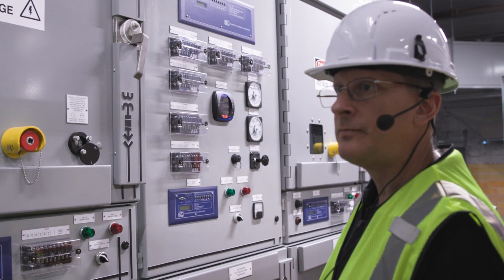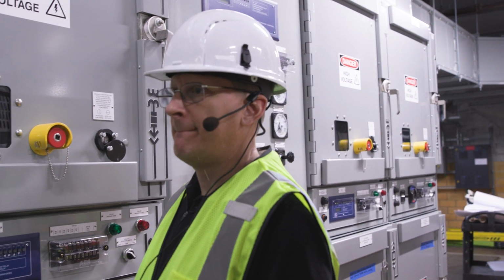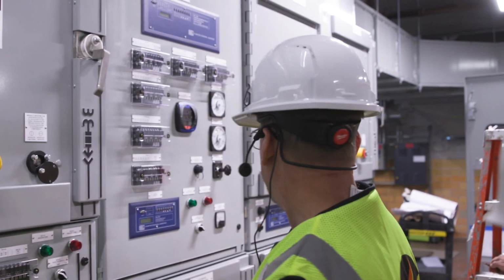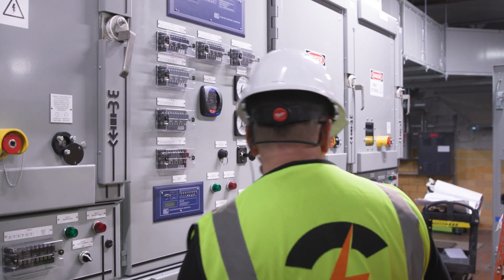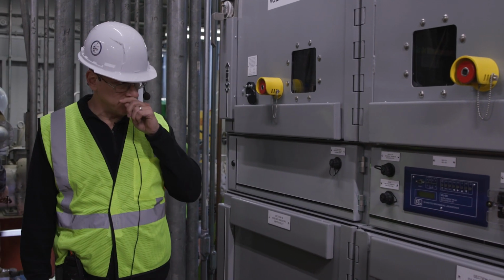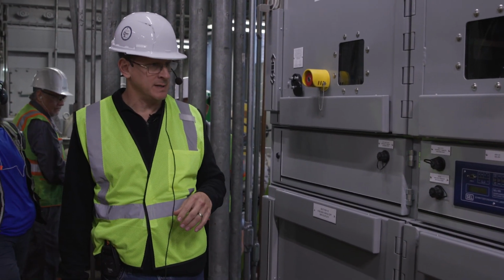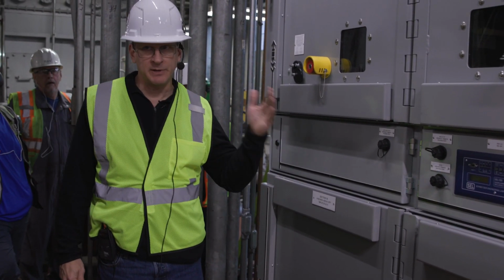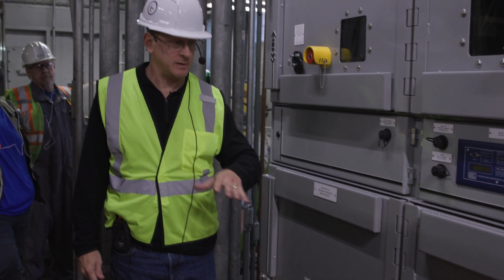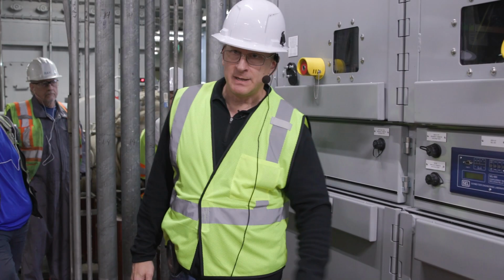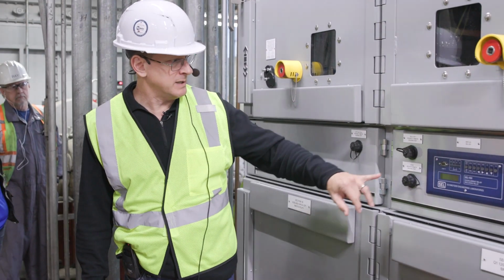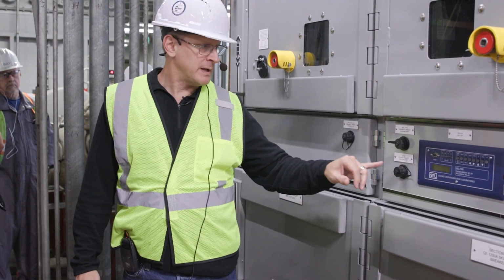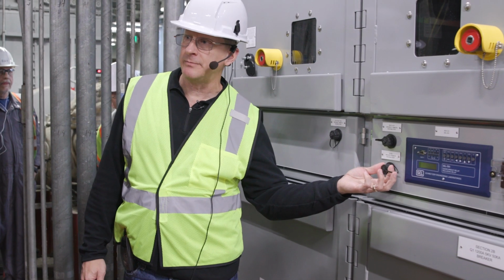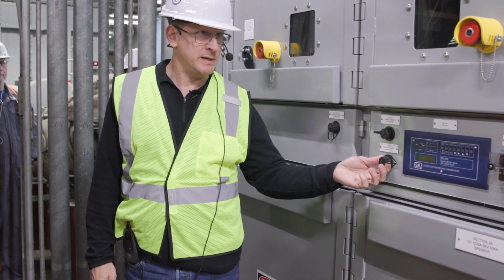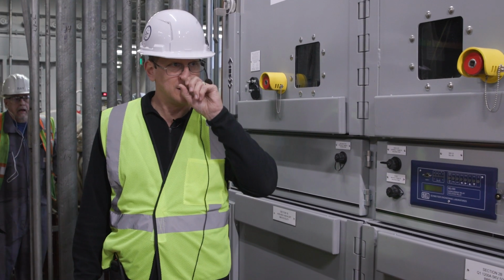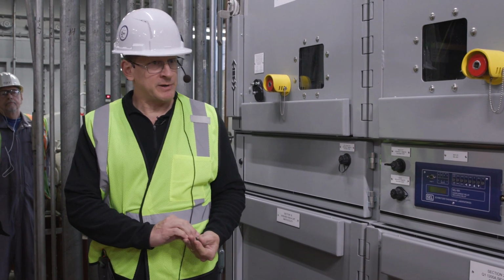Is there a password on that thing? No. Okay, so just turn it on and it just... Yeah. You see if the box is here. The remote racking system means you don't have to manually rack in and out the breakers. There are motors which will do that for you, and there's a box interface that you just plug into these racking ports, and the box is powered directly from the port. And basically, you can give a command to the box to rack in and out the breakers.